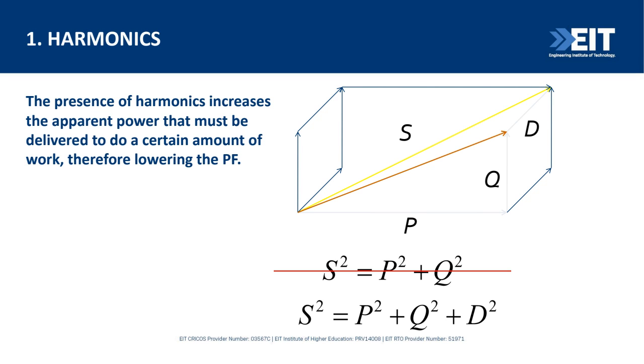When we have harmonics, they increase the apparent power from this green vector to that yellow vector. The apparent power needed to deliver the same active power to households increases, so we need more installed capacity in our system. Rather than S squared equal to P squared plus Q squared, we will have S squared equal to P squared plus Q squared plus D squared. This means that to deliver the same P to customers, you need more installed capacity in the system.